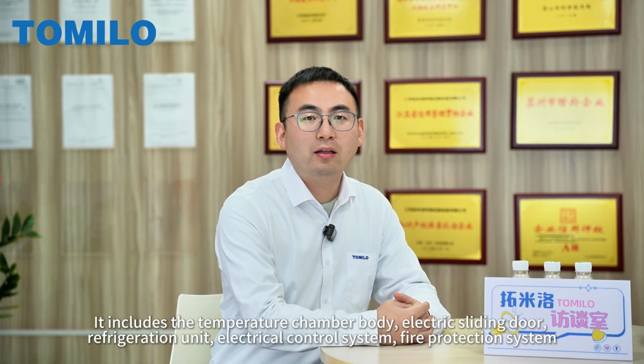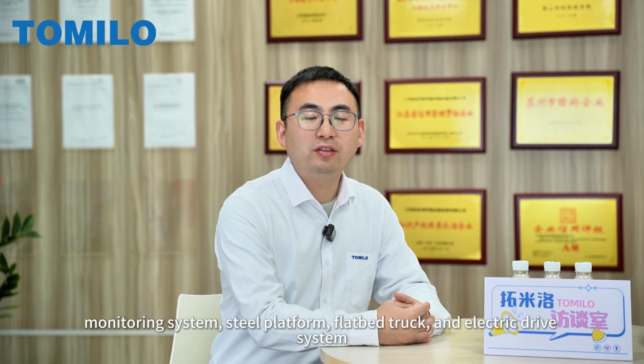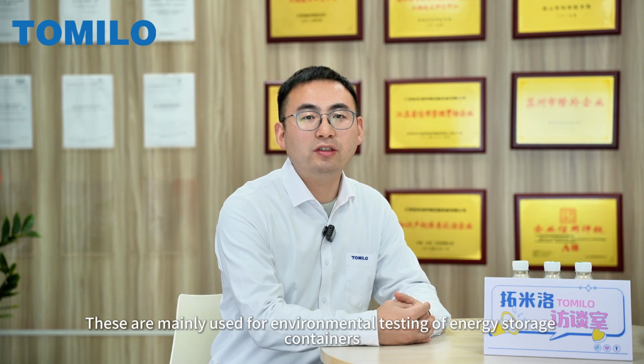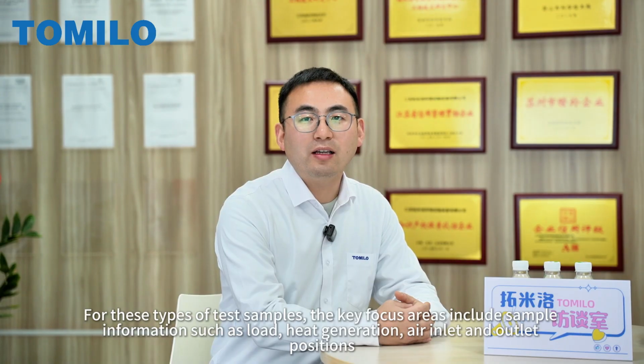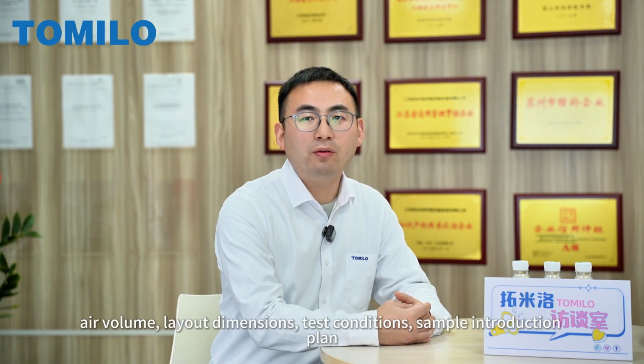It includes the temperature chamber body, electric sliding door, refrigeration unit, electrical control system, fire protection system, monitoring system, steel platform, flatbed truck, and electric drive system. These are mainly used for environmental testing of energy storage containers. For these types of test samples, the key focus areas include sample information such as load, heat generation, air inlet and outlet positions, air volume, layout dimensions, test conditions, sample introduction plan, fire protection design, and external supporting resources.